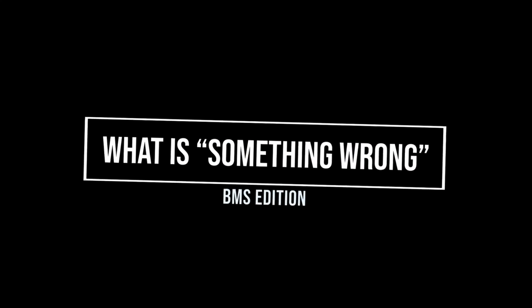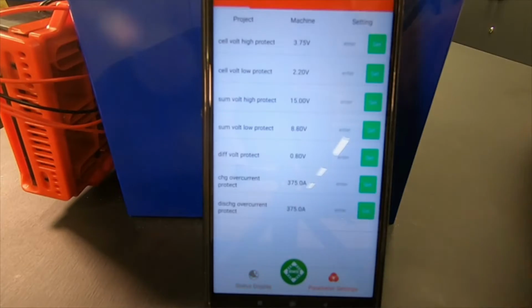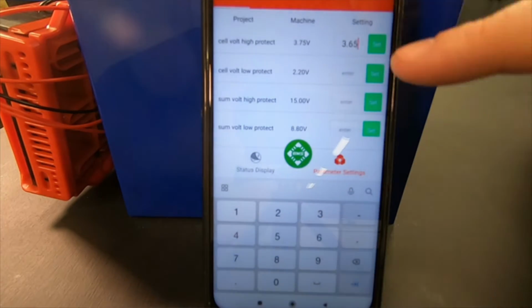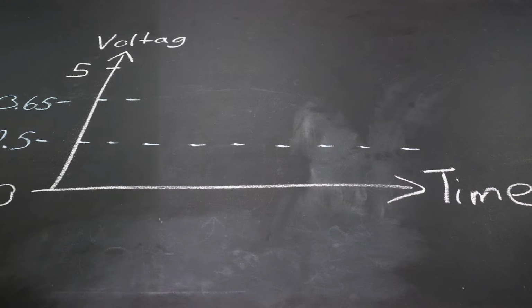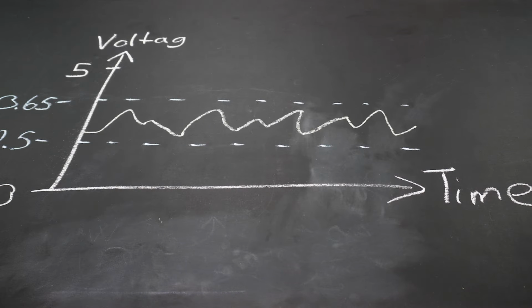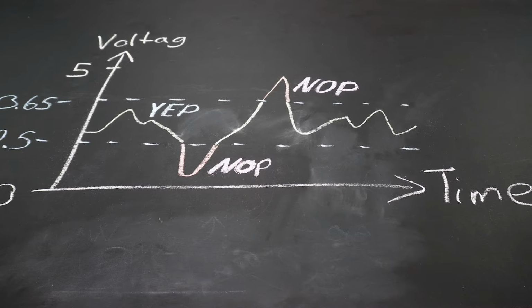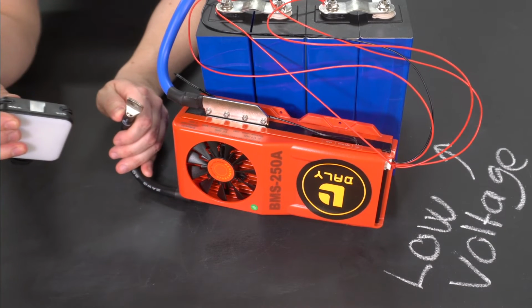That is all fine and good, but how does a BMS actually know that something is wrong, and what does something wrong mean to a BMS in the first place? First, we need to define what something wrong is. We do that by setting what is known as parameters. In this case, we're setting high and low voltage cutoff, which defines a range where the BMS allows the cells to operate. If one of the cells drops outside this range, the BMS is just going to cut the connection to prevent that cell from being damaged. And that's how the BMS knows what something wrong means.